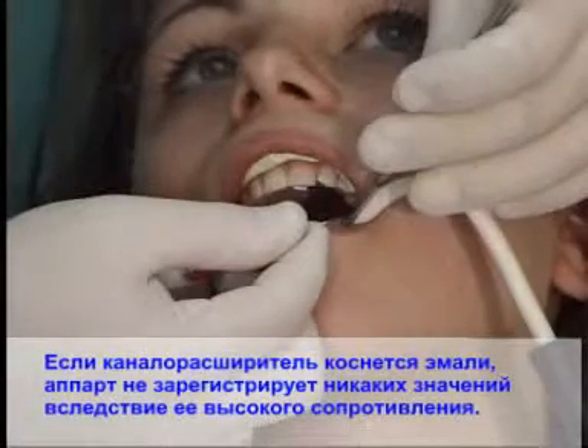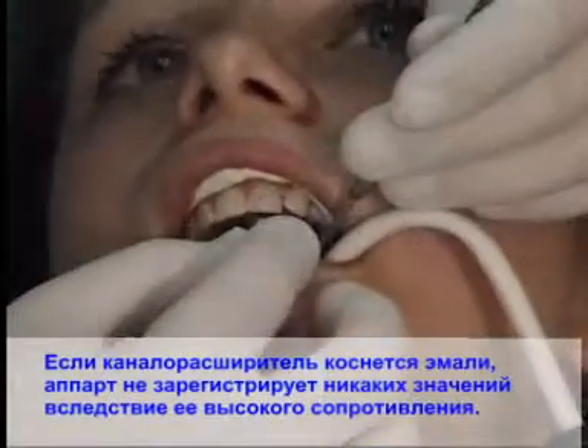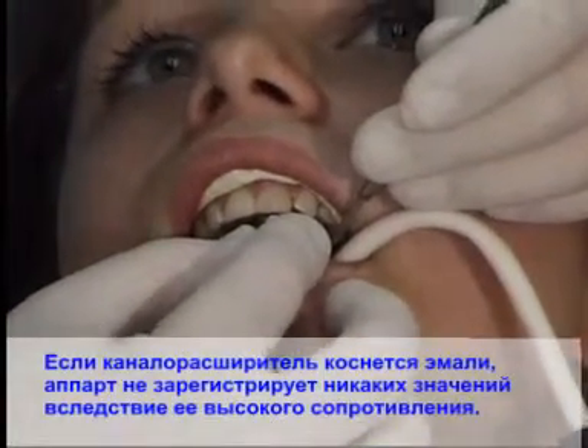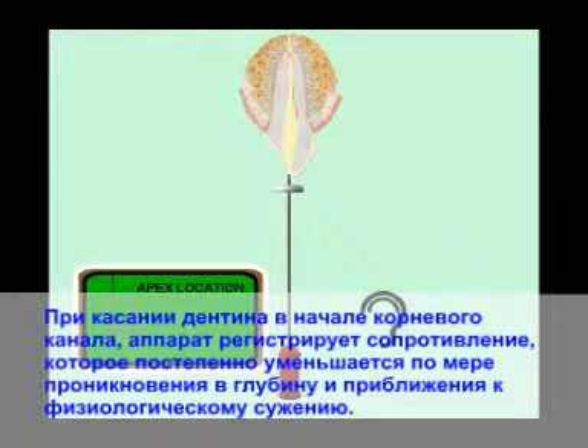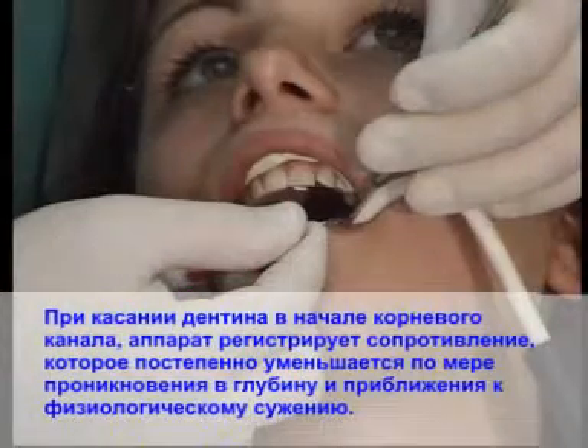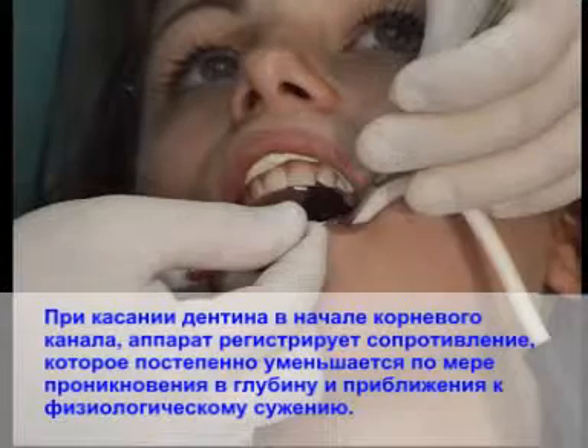If the canal widener touches the enamel, the device doesn't register any grades because of the enamel high resistance. If the canal widener touches the dentin at the beginning of a root canal, the device registers resistance, which gradually decreases with penetrating in deep and reaching the physiological narrowness, foramen physiologicum.